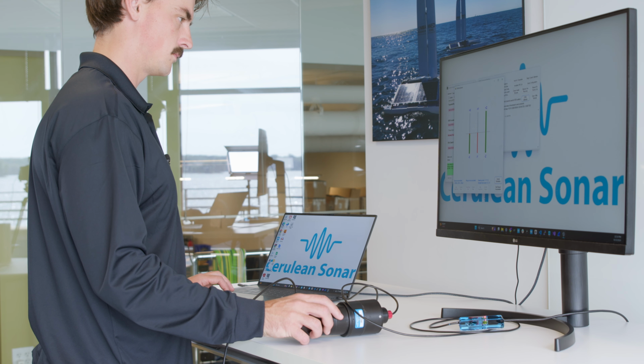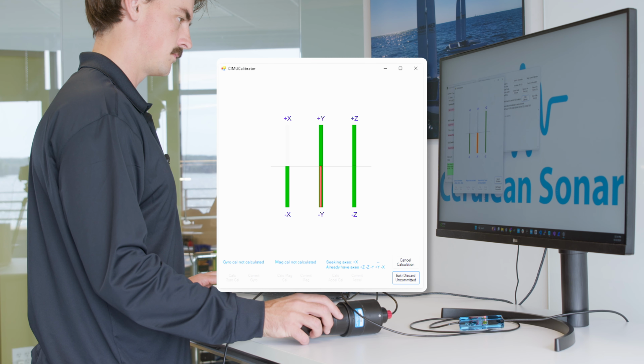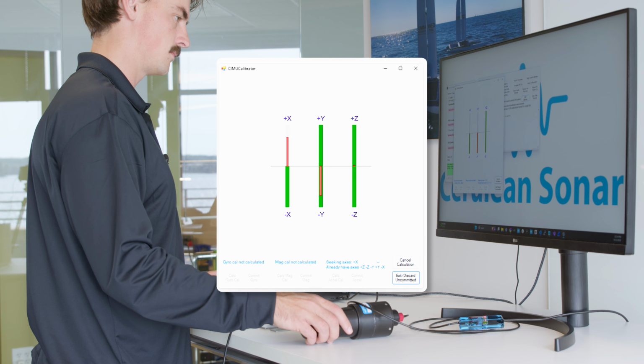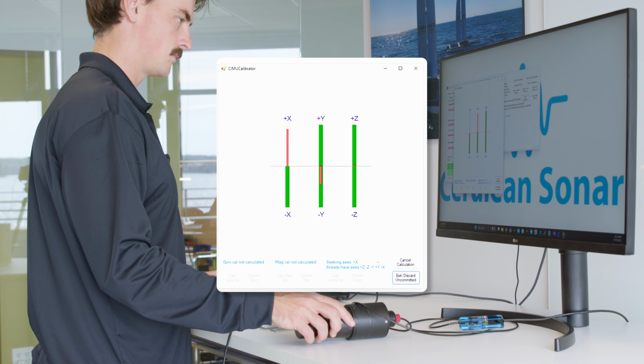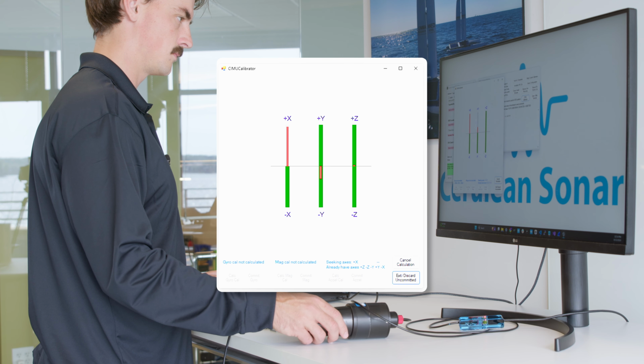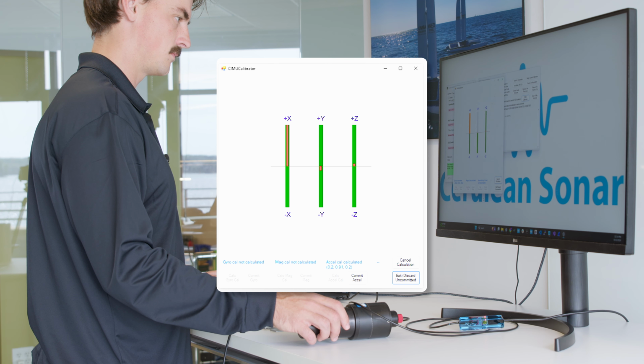The background color of each axis gives a visual guide. A gray background means the axis still needs to be collected. An orange background shows gravity is aligned, but the device needs to remain stable a bit longer. A green background confirms the axis data has been successfully collected. Once all 6 axes are collected, you can click the Commit Accel button to complete the calibration.